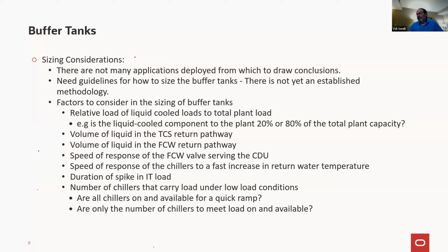So you brought up an interesting issue, and had we gone with liquid cooling the way I thought we would 10 years ago, in which we continuously raised the temperature of the media, we could eliminate the chillers. The chillers are the problem. The whole purpose of the buffer tank, as I'm talking about at this point, is to service the plant, not the other way around. The thermal storage services the IT load to make sure it stays up. The buffer tank is in service of the cooling plant.